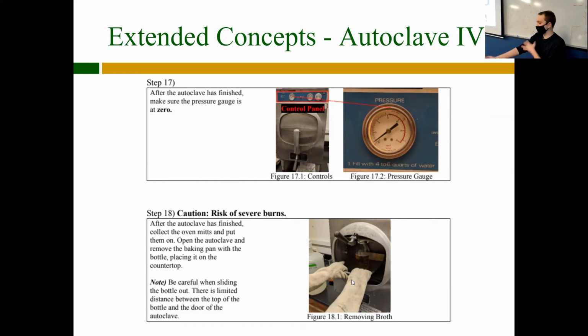So be careful, put on gloves when you're pulling it out. We have gloves sitting right next to the autoclave. They're always there. They're especially long. They go up to around your elbow. So put those on and very carefully pull out your sample. Make sure once again that you're careful, especially when this is so hot, because this lid, if it gets touched, if it gets flipped over, and then that almost boiling liquid falls into this container on your hands, it's going to hurt a lot. So yeah, be careful, risk of severe burns.